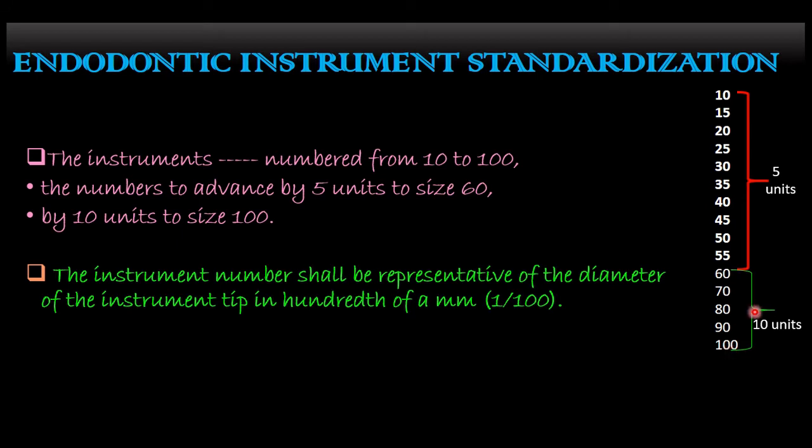The instrument number will tell about the diameter of the instrument tip in hundredths of a millimeter. For example, instrument number 20 will have a tip diameter of about 0.20 mm at the tip, instrument number 10 will have 0.10 mm at the tip, and number 15 will have 0.15 mm at the tip.